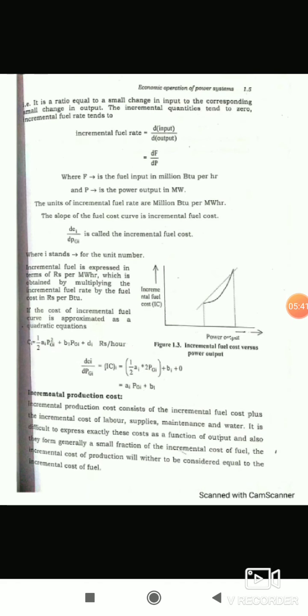Next, it is the ratio equal to this small change in input to the corresponding small change in output, as the incremental quantities tend to 0. The incremental fuel rate is equal to the change in input by the change in output, that is equal to dF by dP, where F is the fuel input in million BTU per hour and P is the power output in megawatts. The units of incremental fuel rate are million BTU per megawatt hour. The slope of the fuel cost curve is the incremental fuel cost.